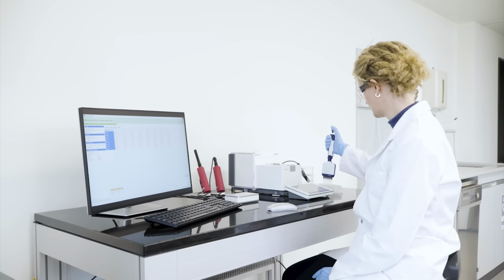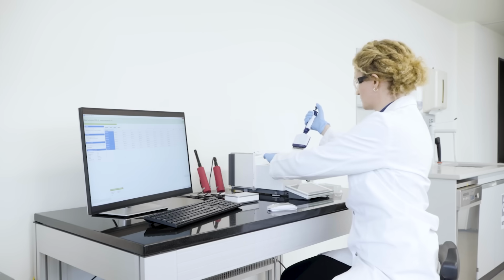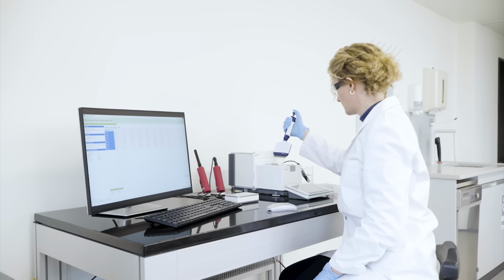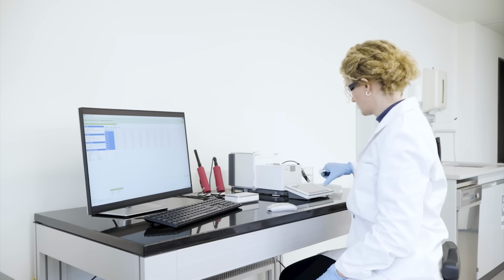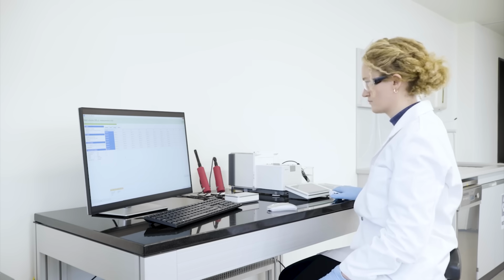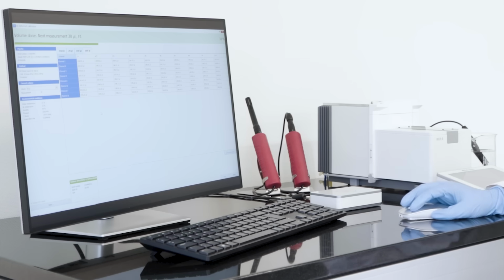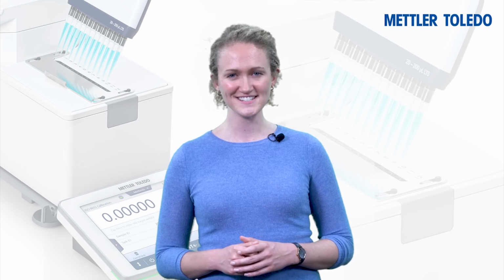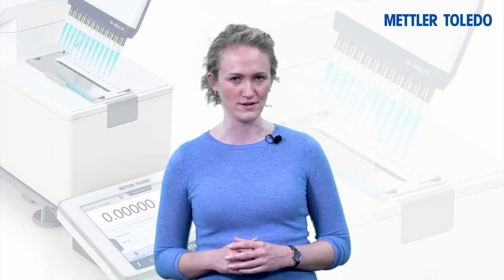The supplementary Calibry PC software guides you step-by-step through pipette calibration procedures in order to ensure accurate and traceable calibrations according to ISO 8655, JJG 646, and 21 CFR Part 11. Now, let's take a look at how easy it is to complete a calibration with the MCP and Calibry.